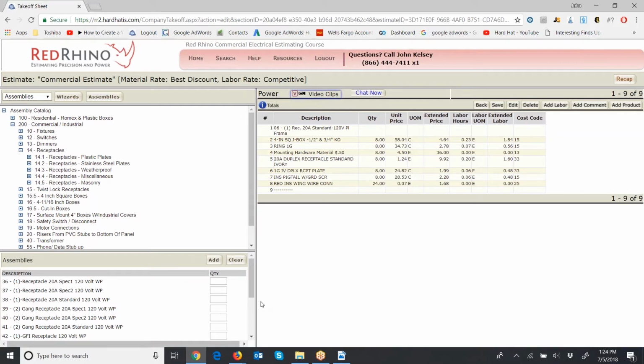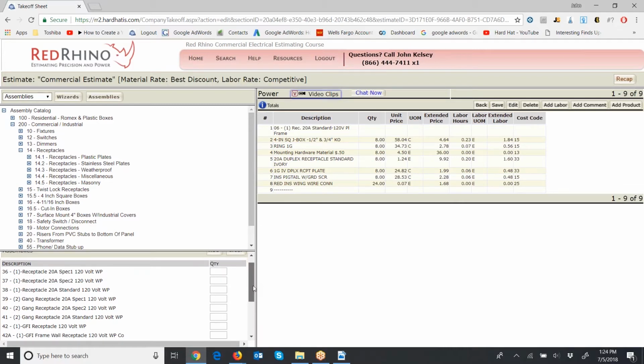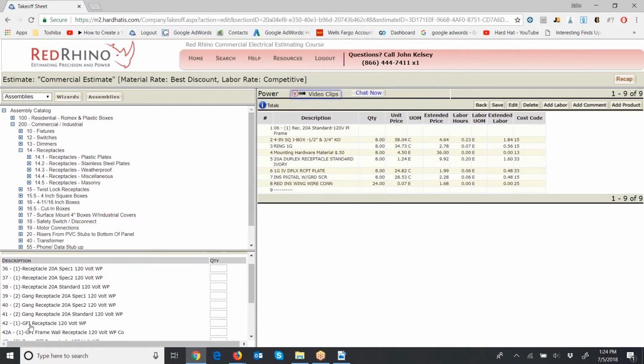Now I'm going to scroll down real slow and show you what that is. See, we have a receptacle GFI. Here's a 1-gang GFI receptacle, 120 volt, weatherproof. Now you don't know this by looking, you'd have to input this receptacle assembly to know this, but I happen to know that that assembly right there is going to be a bell box with a bell box cover. We want the one that's a framed receptacle with a weatherproof cover.